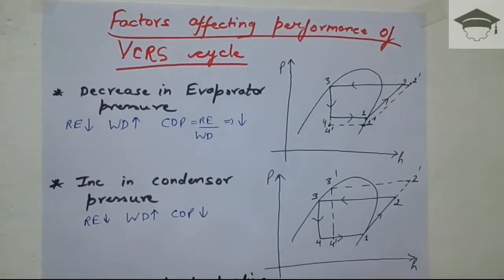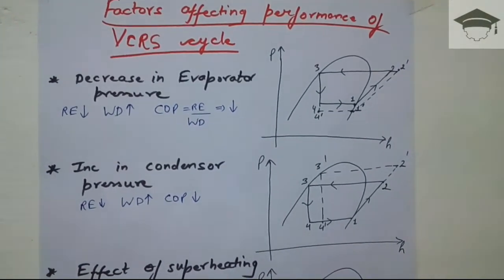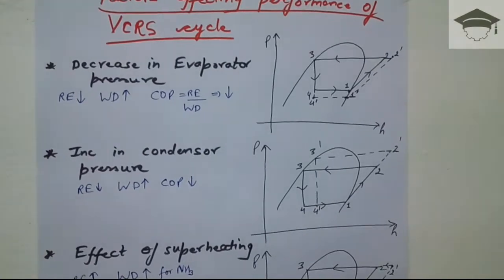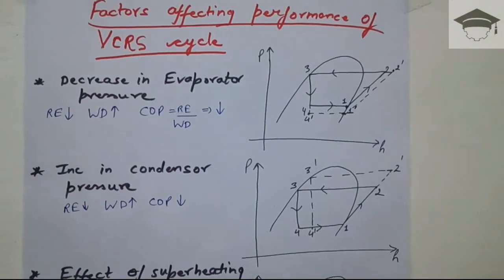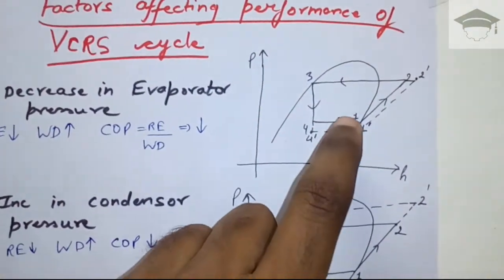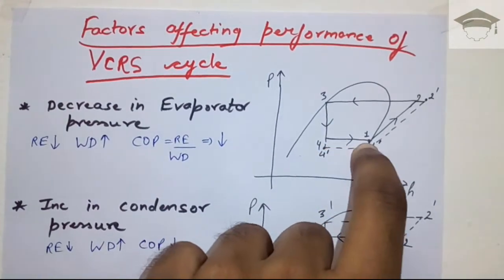The VCRS cycle — that is, the vapor compression refrigeration system cycle — mainly depends on four parameters: evaporator pressure, condenser pressure, superheating, and sub cooling. First, let us take evaporator pressure. This is drawn on a p-H, that is, pressure-enthalpy diagram, which makes it easy to understand.